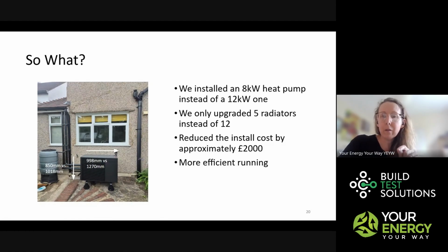So a lot of these installs are going in, and we're not really getting a good picture of how well they're running. We install the Homely smart thermostat with our Samsung heat pumps. There are a number of other smart thermostats out on the market. What that lets us do is look at a few of our recent installs when it's very cold, and check whether they are running at the flow temperature that we would expect.